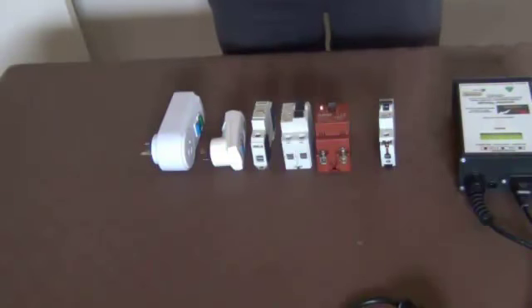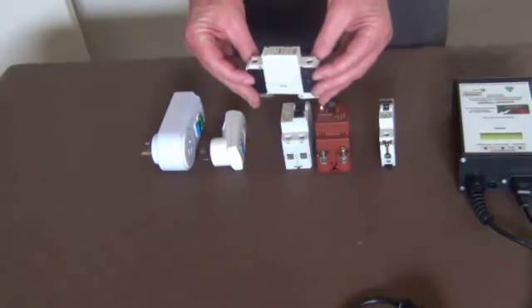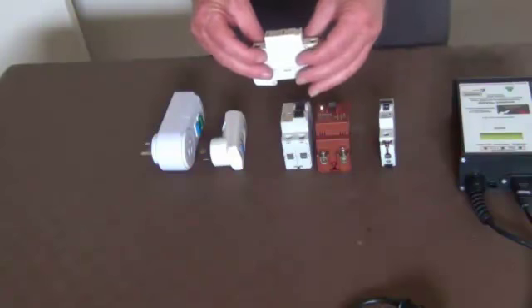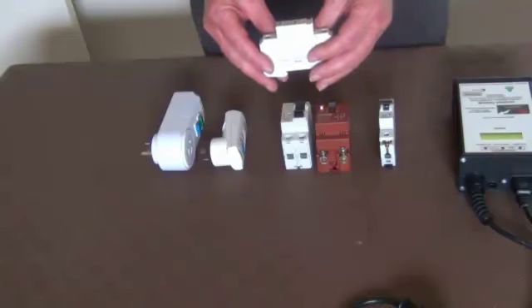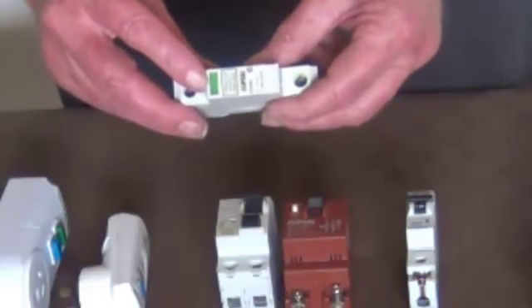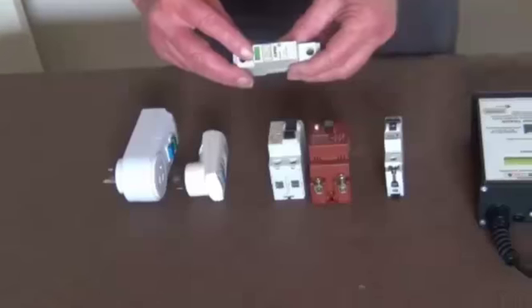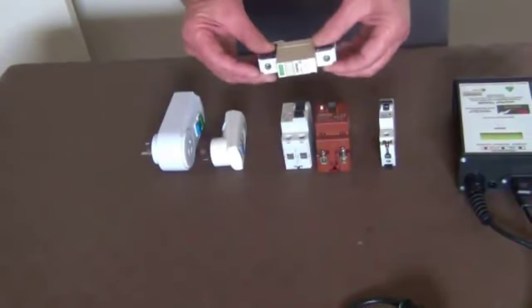Alright, so this time we're going to have a look at some protection devices. I have a range of them here. Some are people protection, some are circuit protection, and some are over voltage protection. There are basically three types. We'll deal with the over voltage protection first, surge protection, metal oxide varistor, voltage dependent resistor, whatever you like to call them. This is a switchboard mounted one, DIN rail mounting. It just sits on your switchboard. It's got a green light there, and its purpose is to clamp any voltage above about 375 volts. If it gets damaged, in theory that will turn to red and tell you that it needs to be replaced. So that's the surge protection or voltage dependent resistor.